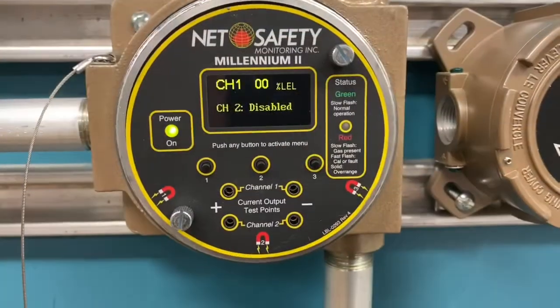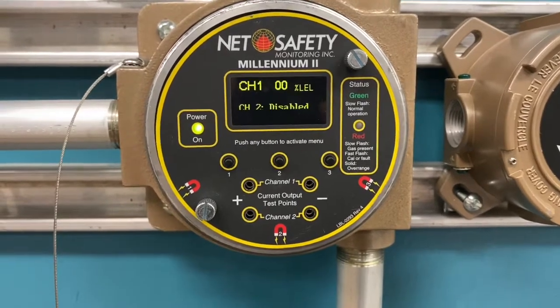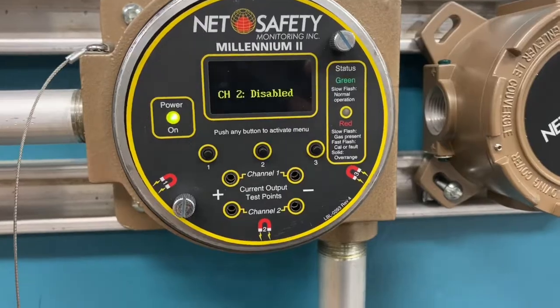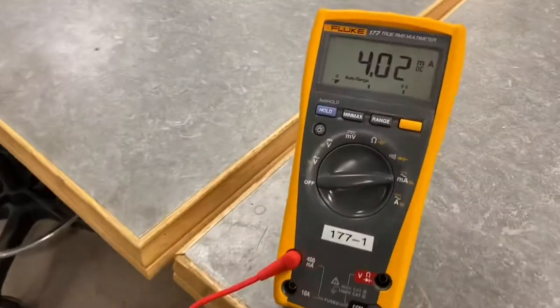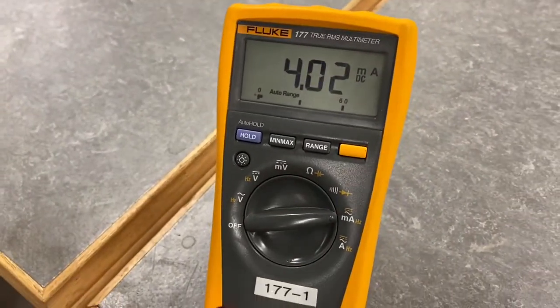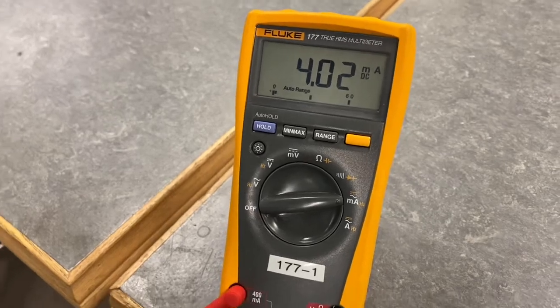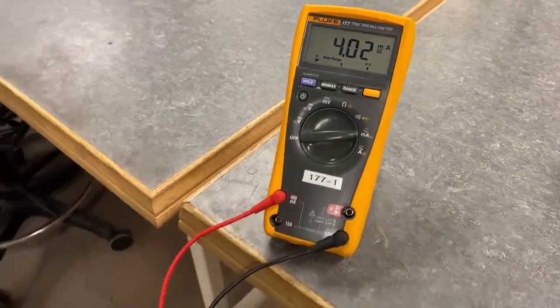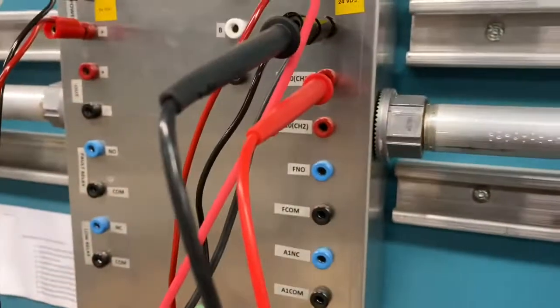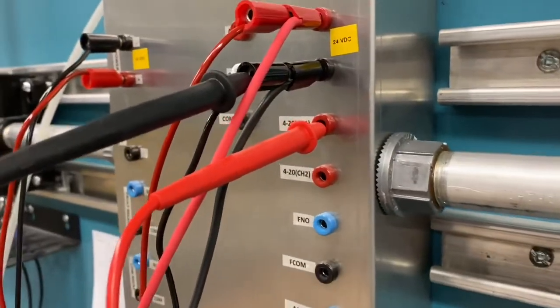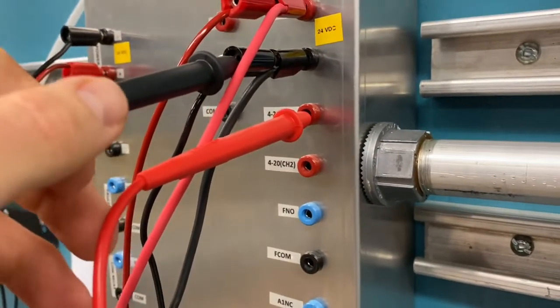One last thing I wanted to showcase is back over on the Net Safety Millennium 2 controller. Right now it's reading 0 LEL. I've hooked up a multimeter across the 4 to 20 milliamp signal, and you can see it's reading 4 milliamps, which it should at 0% LEL. I'll show you where I've got that connected over on our box here. You can see what I've basically added.